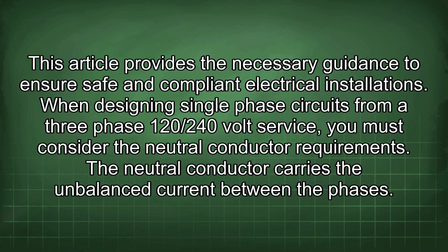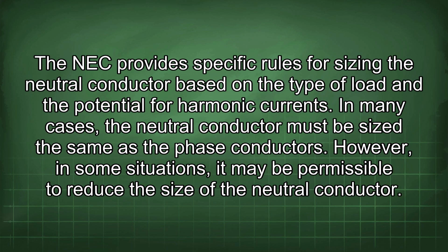When designing single-phase circuits from a three-phase 120/240-volt service, you must consider the neutral conductor requirements. The neutral conductor carries the unbalanced current between the phases.